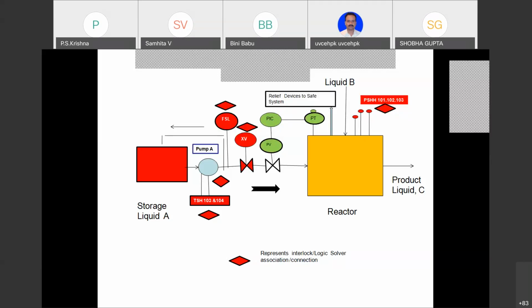And then we found that we have to introduce 3 pressure switches instead of 1. Why? Because we said we are going to introduce what is known as a voting system. What are these pressure switches supposed to do? When the pressure goes to 45, it should shut down the system. What is shut down? The XV should close, this pump should shut. That's the job of the logic controller.